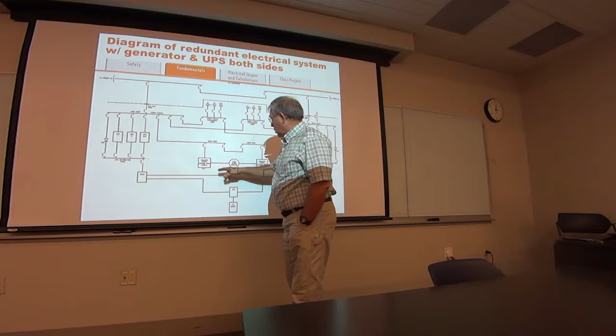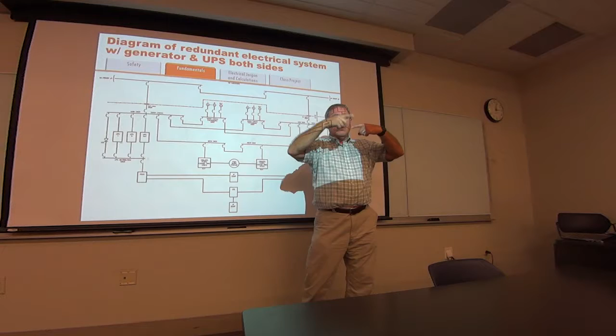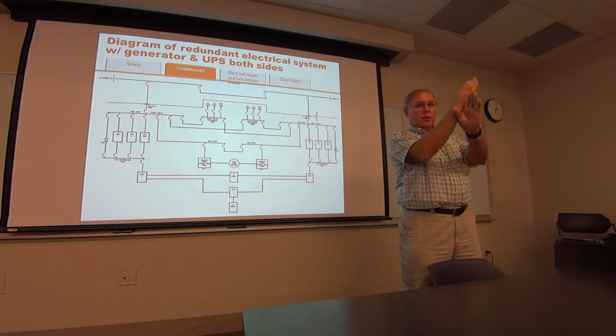But that ain't the way it happens. Amazon or Google, I don't know which one it was, had a big outage. Something happened to the power, and the generators came on, and they're parallel. They crank up, and when they get parallel, when the AC waveform gets in sync, they're all running at slightly different speeds. When they get in sync, they close them in. They got a synchronizer, within 10 degrees. Come to find out, the synchronizing relay, which is a single point failure, wasn't working. They never would come online.